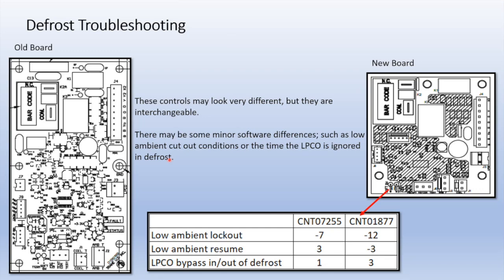And what that does is two things. When you have a low ambient lockout, it's going to lock out the compressor so the heat pump can't run below -12 Fahrenheit. And it's going to send X2 back to W1 so that Y signal goes to the outdoor unit, doesn't turn the outdoor unit on, comes back and turns the furnace on during that lockout. The other thing it's going to do is during a defrost, it energizes X2. So that heat developed from the gas furnace is going to go into that indoor coil and really help with a defrost by adding so much heat to the refrigerant.